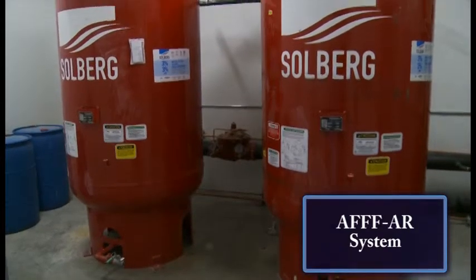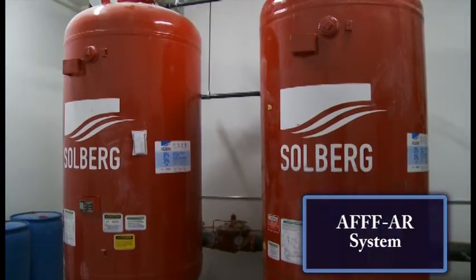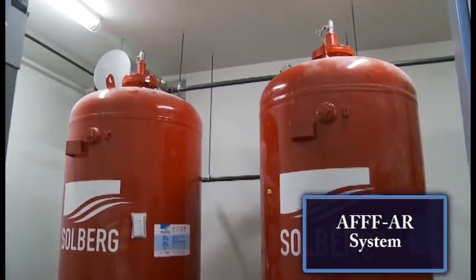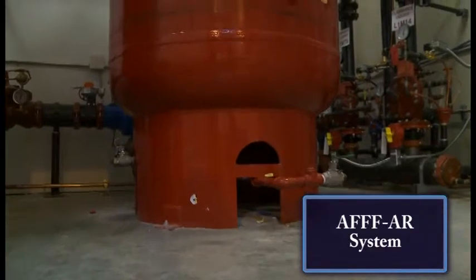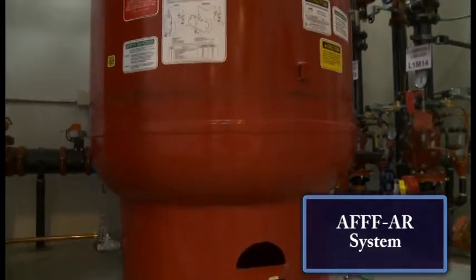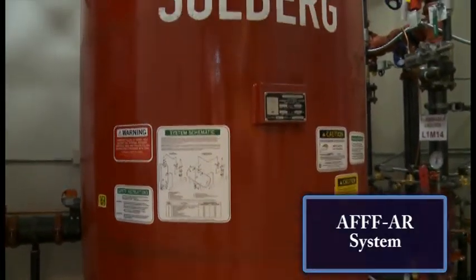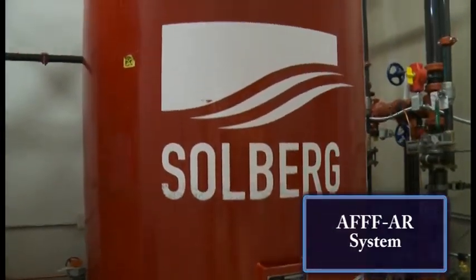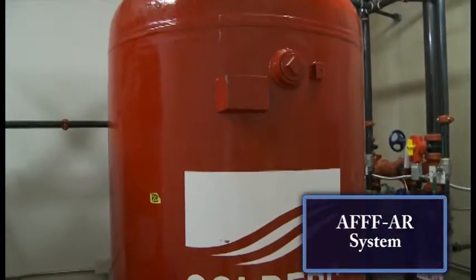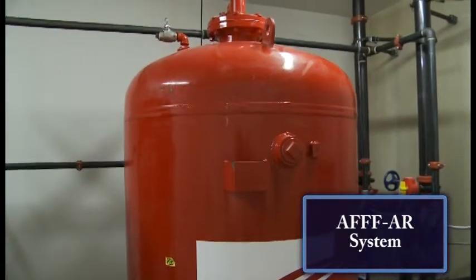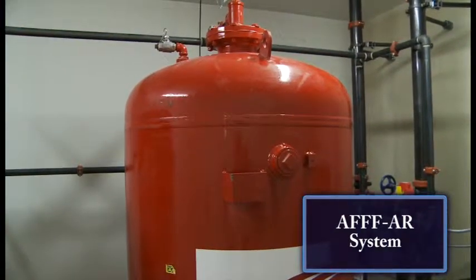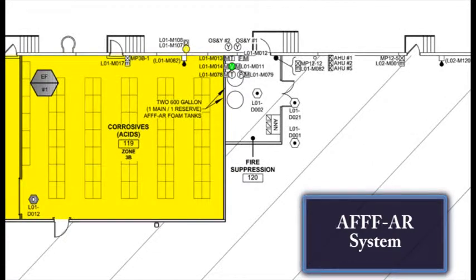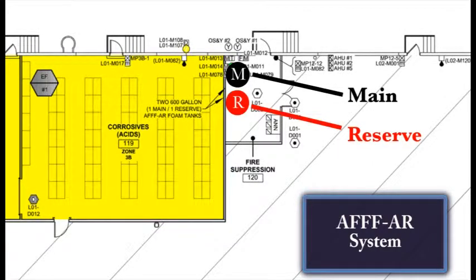A single cache of AFFF-AR concentrate is stored in 2 vertical tanks, a main and reserve tank. It is used to supply AFFF-AR concentrate to the flammable liquid storage area through a dedicated alarm valve. The reserve tank would be used to protect the flammable liquids room in the event that normal operations can be restored to the space after a foam discharge. For example, the reserve tank could be used to coat the interior surfaces of the space through any open foam sprinkler heads prior to sending in firefighting personnel into the space after a foam release.